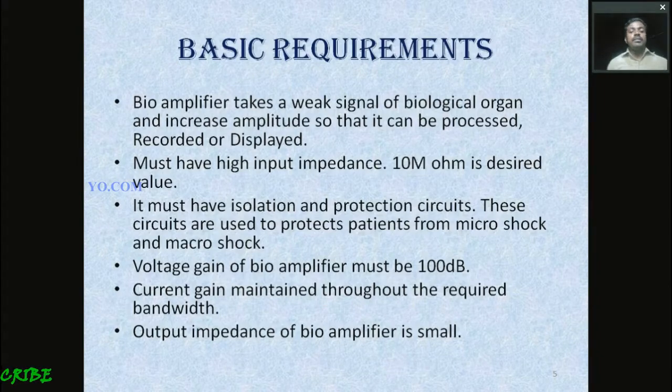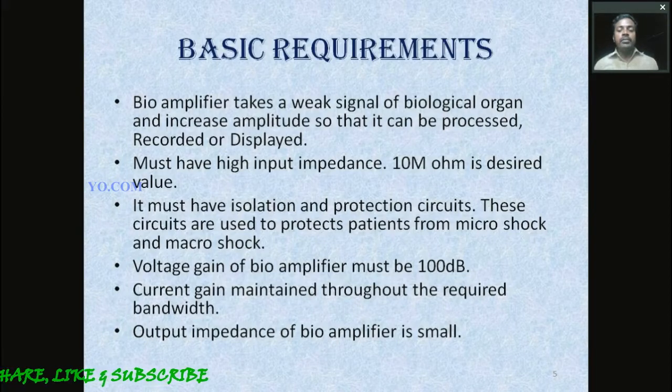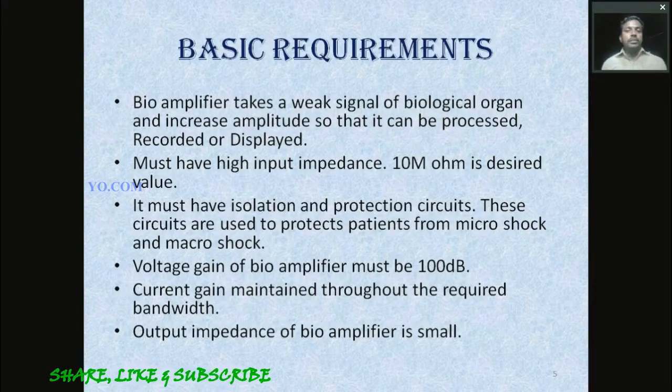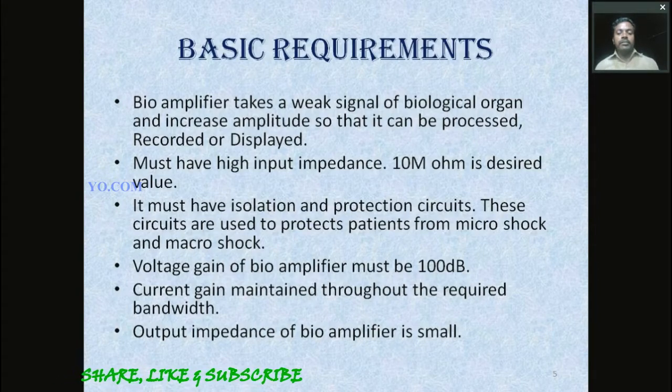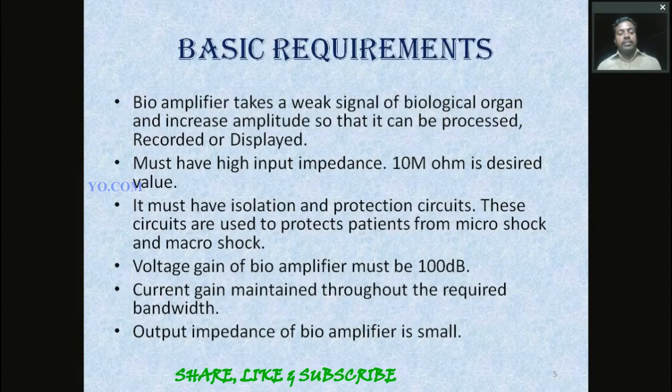So the bioamplifier must have high input impedance. That is important, but we already discussed it. To have high input impedance, approximately 10 megaohm is the desired value. So the input impedance should be 10 megaohm. A megaohm is a very large resistance in electronics. So the input impedance is very high.